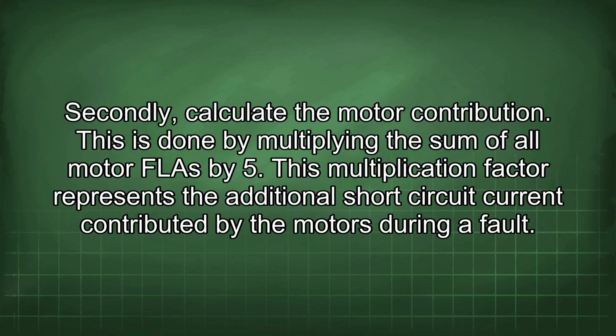Secondly, calculate the motor contribution. This is done by multiplying the sum of all motor FLA by 5. This multiplication factor represents the additional short-circuit current contributed by the motors during a fault.